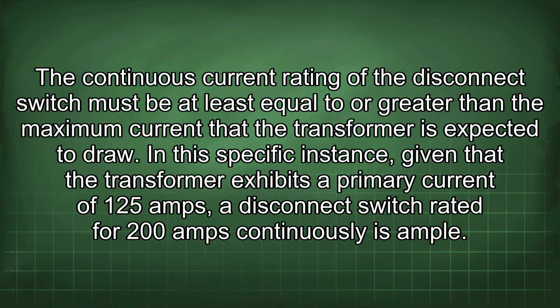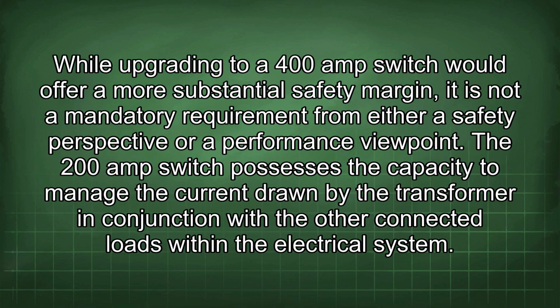In this specific instance, given that the transformer exhibits a primary current of 125 amps, a disconnect switch rated for 200 amps continuously is ample. While upgrading to a 400 amp switch would offer a more substantial safety margin, it is not a mandatory requirement from either a safety perspective or a performance viewpoint.